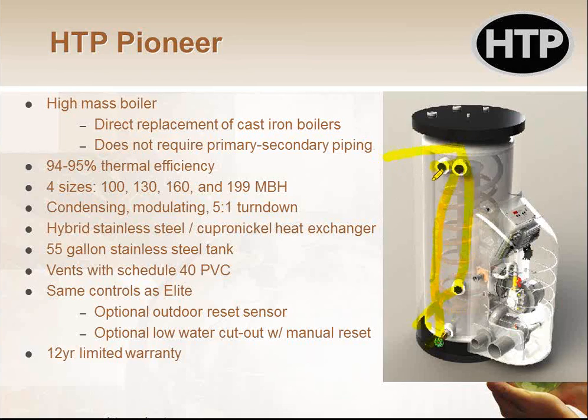Actually, it's coming in the bottom and going out the top. Right? But there's very low pressure drop on the water side. I basically got a 2-inch pipe coming in and a 2-inch pipe coming out. It's a big open drum in the middle. So the low pressure drop means I don't have to do the primary, secondary piping. I still got to do the PVC venting, so there's still a little bit of work for me to do. But at least I don't have to change the piping arrangement around.